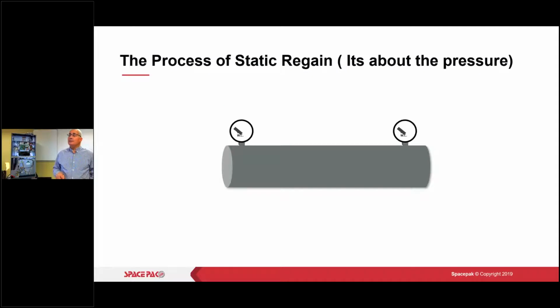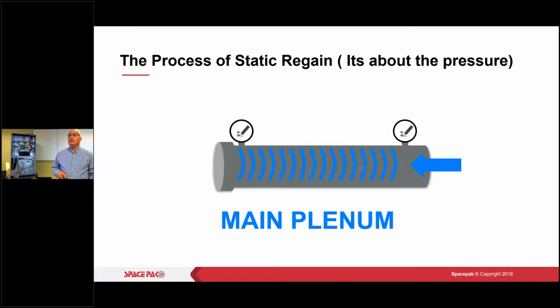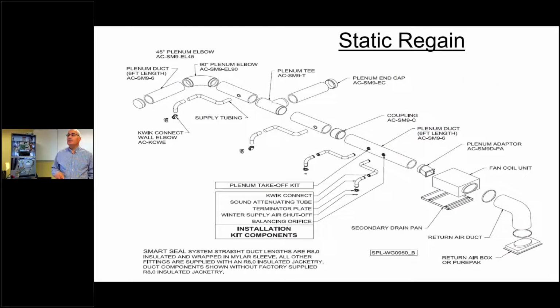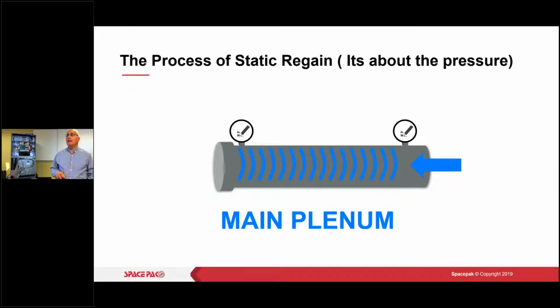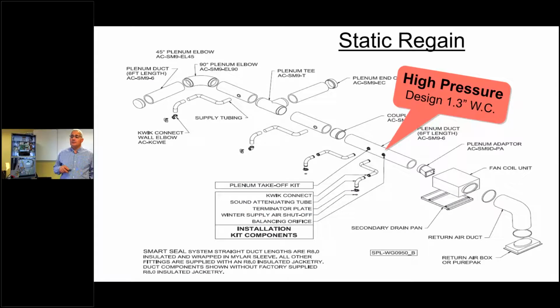So what we're talking about here with static regain, since I'm capped off at the end of my plenum, right, and we put the air through the plenum, what we should have is the same pressure from the front, whoops, back up, from the front, too fast on the clicks, as into the back of the plenum. And then I'll have equal flow rate coming out to my drops. All right, so there's our typical layout of our system. You can see we'll have high pressure in there, so we designed to 1.3 water column. And I can go into a lot of detail right here, right now.